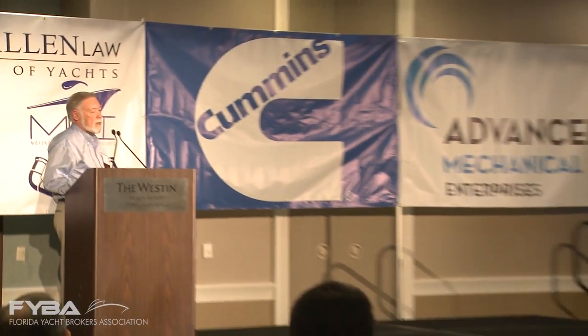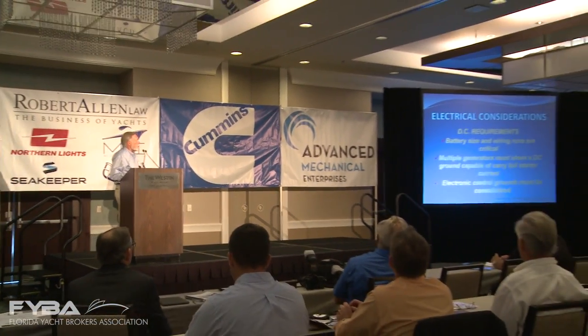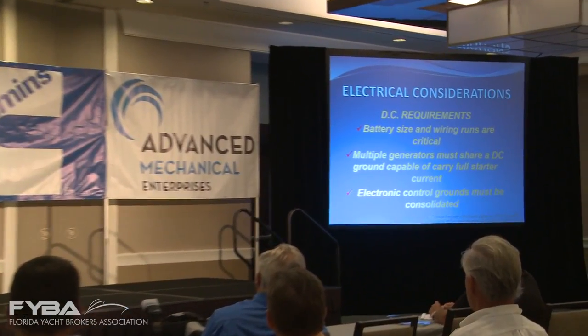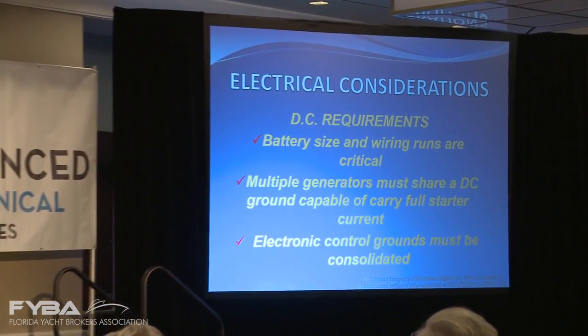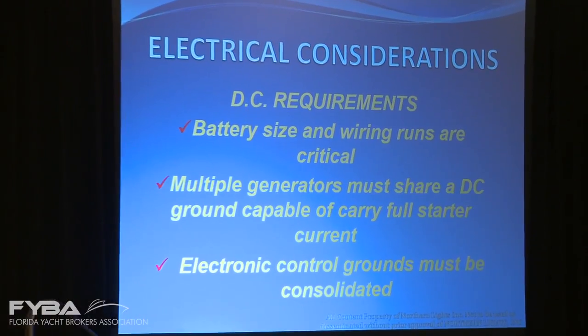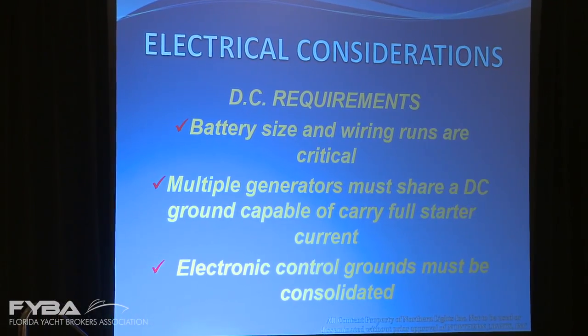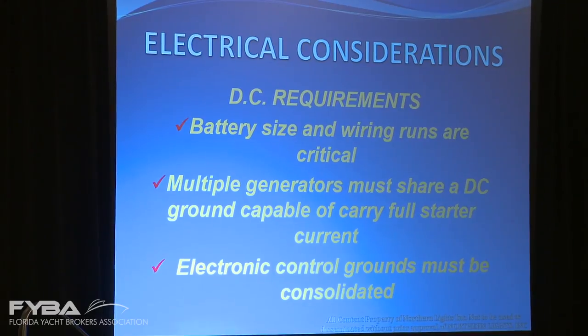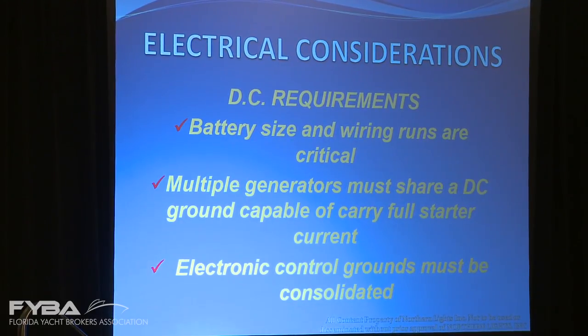In terms of DC requirements, battery size and wiring runs are a big deal, and on a lot of big yachts the batteries may be located a long ways away from the mechanical equipment. This can be a problem. It's usually not too big a problem, but the generator manufacturers specify how long the wire runs can be and what size the cables are supposed to be, and that's in the application guides the manufacturers supply.